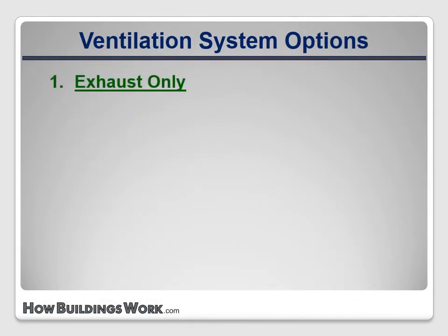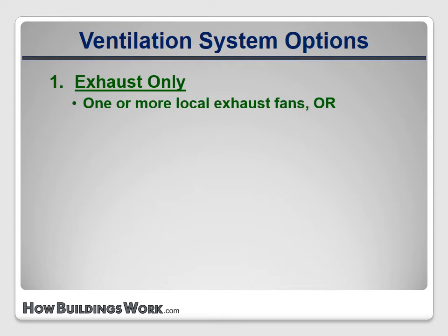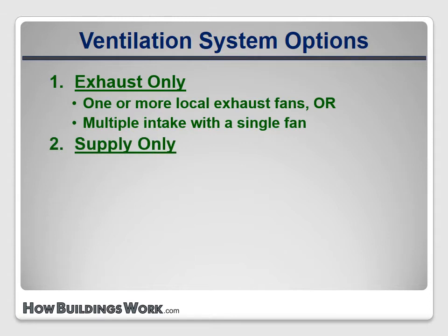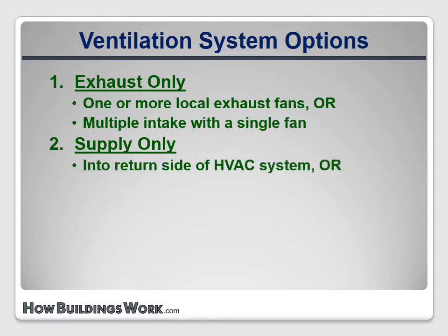Exhaust only systems use one or more fans to remove stale air from the building. They depressurize the building so fresh air enters through leaks in the envelope. These can be local fans that pull air out of a single space, or fans that draw from multiple spaces. Supply only systems use one or more fans to push fresh air into the building. They pressurize the space so stale air is pushed out through leaks in the envelope. These may use the air handler fan to draw air in through a fresh air intake, or they may use dedicated fans.